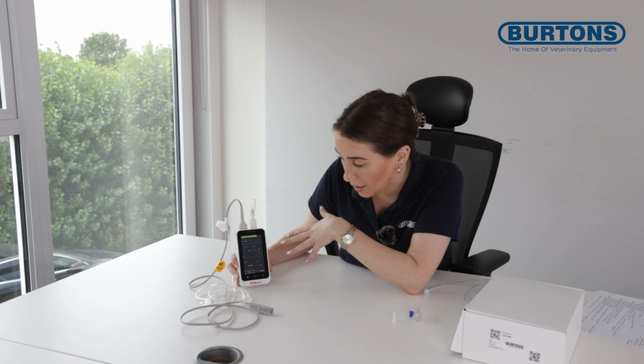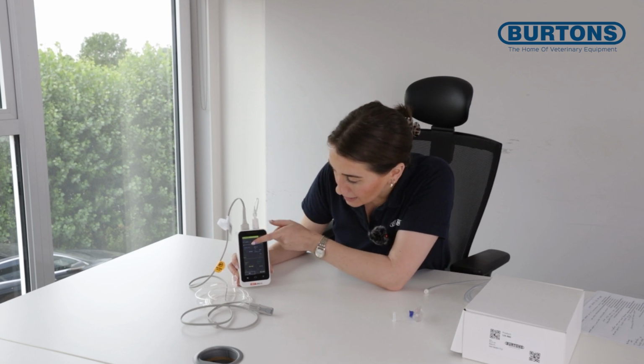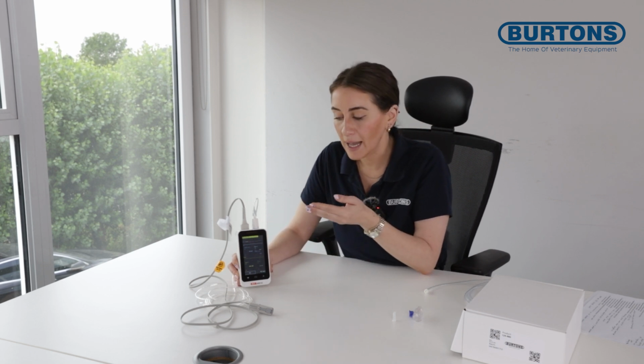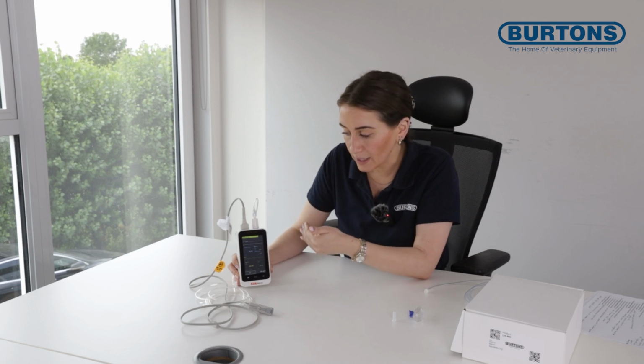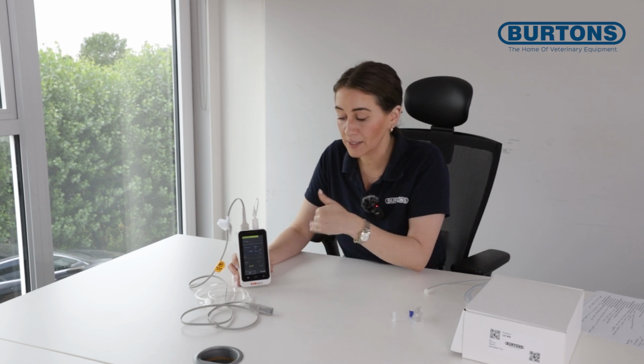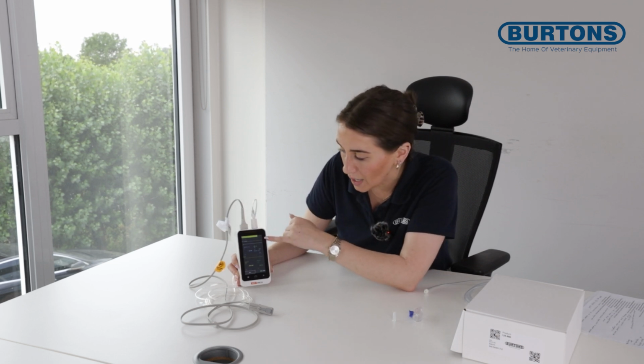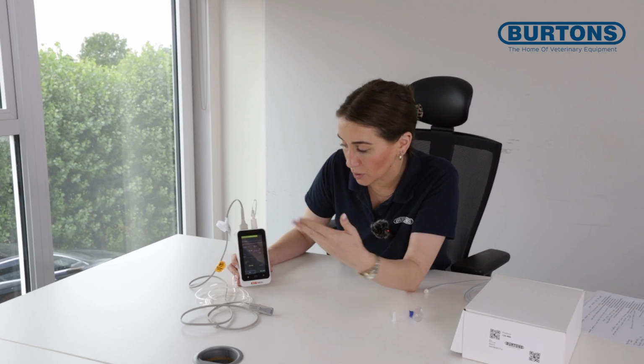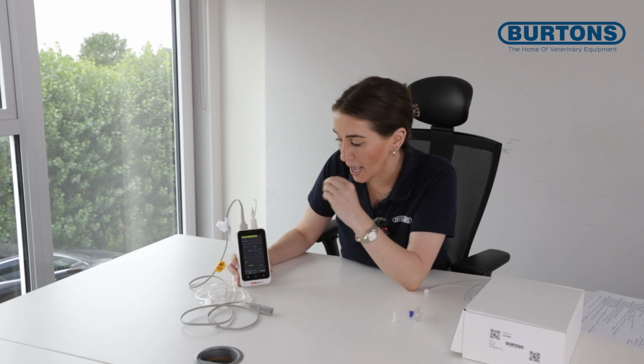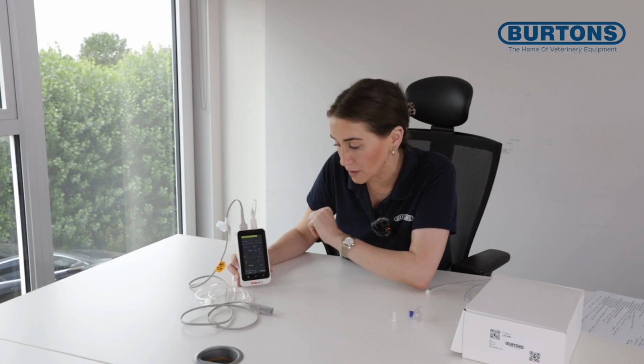We can alter different parts of the CO2 and the graph itself. Currently it's set to 61 millimeters of mercury, so we can raise that higher to monitor higher levels of CO2. However, typically we always want our CO2 to be lower than 61, so it's not often helpful to have a smaller graph with higher numbers. So it will just change, alter it, and we'll go through that in a minute, how your graph looks on the screen and where it rises and falls as such.